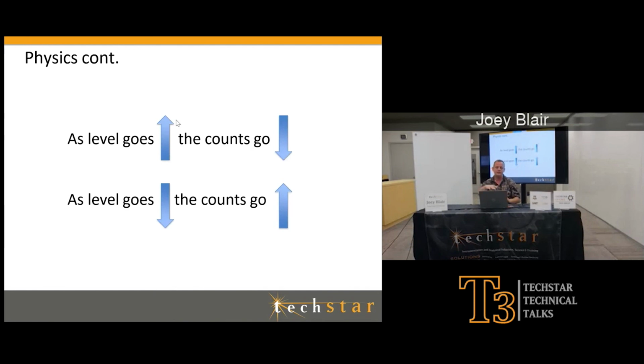And as that vessel fills up, it's going to repeatedly do the exact same thing every time. So that 150 counts could be off a little bit, 5% or so in the middle somewhere. I could be off 5% or so in the center of my measurement. But for the most part, I am going to be pretty accurate. So a lot of times for 100%, we will do a closed shutter. I always prefer to fill my process up to that point, because what if a little bit of radiation is coming through my process?